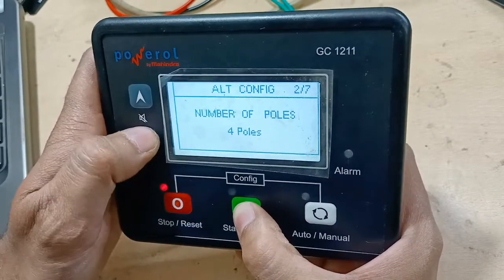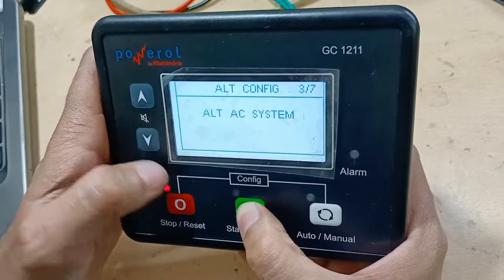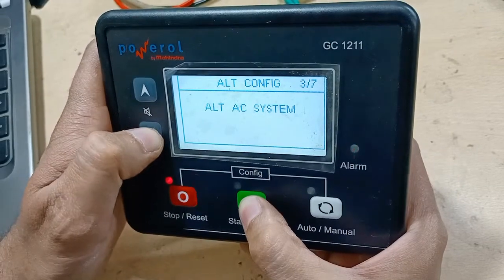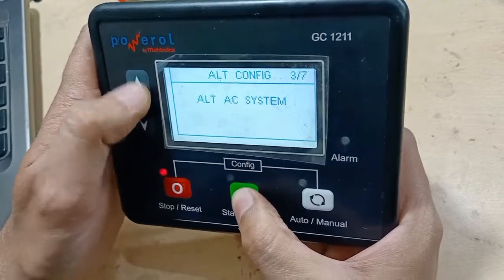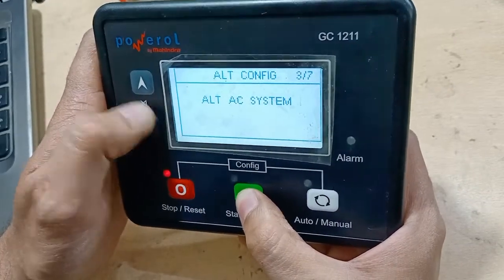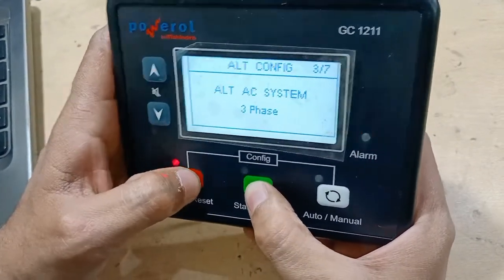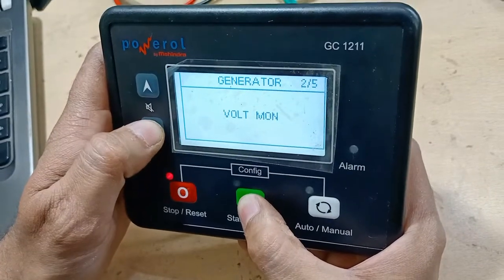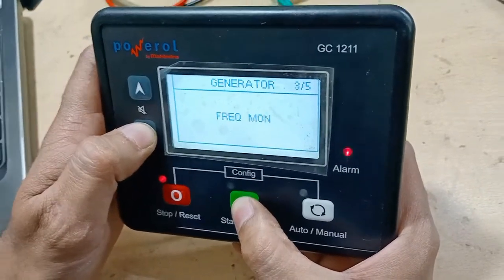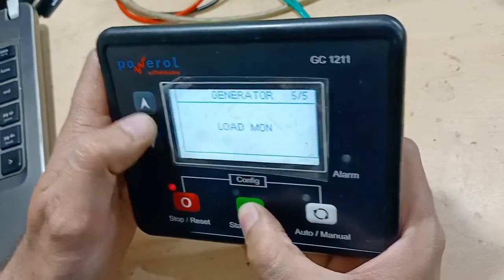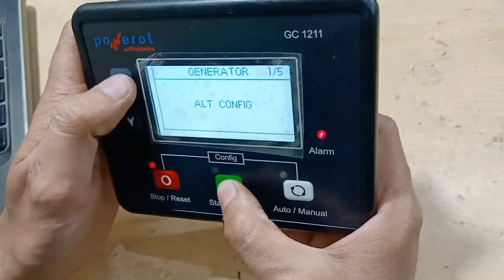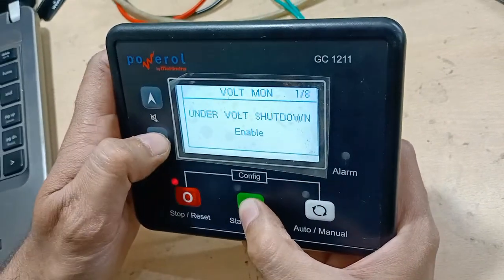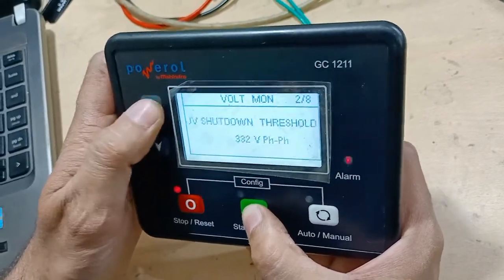Next is the generator and alternator configuration. You can set the number of poles and phase — whether your DG is single phase or three phase. You can change it from here. We will leave it as three phase. Voltage monitor, frequency monitor, current monitor, and load monitor settings are also available here.